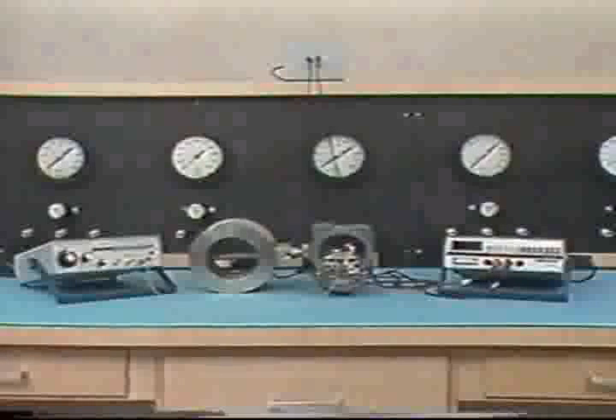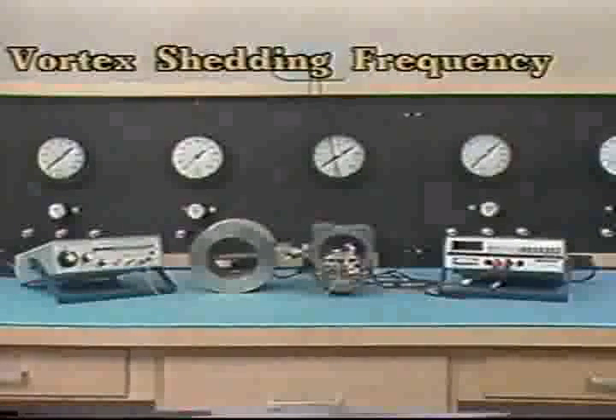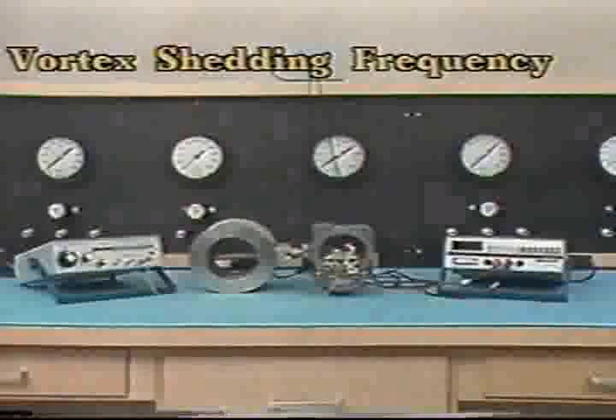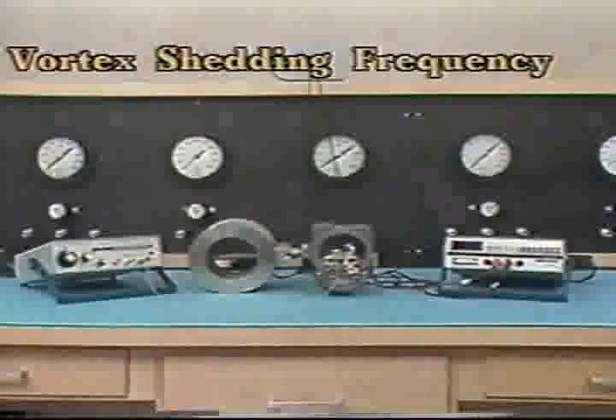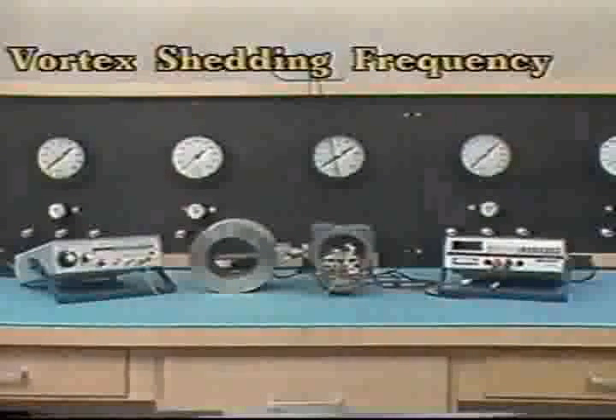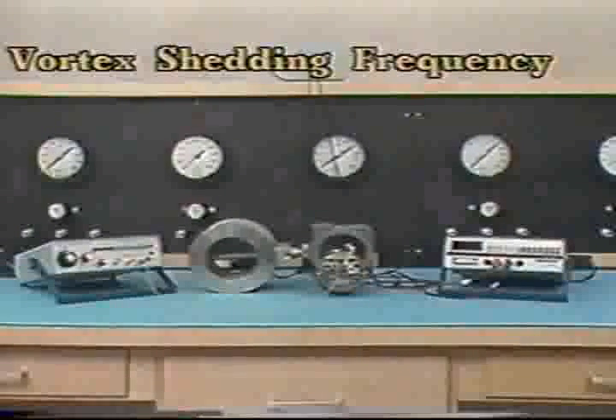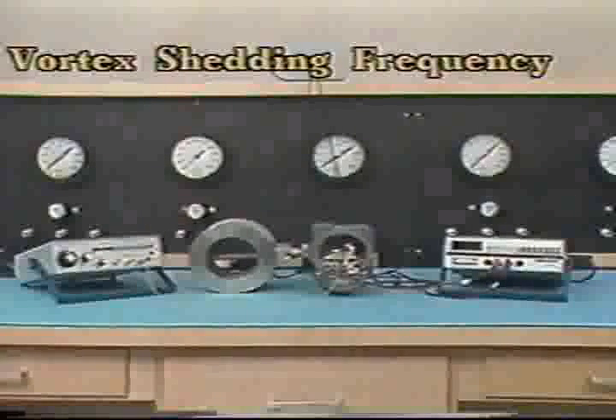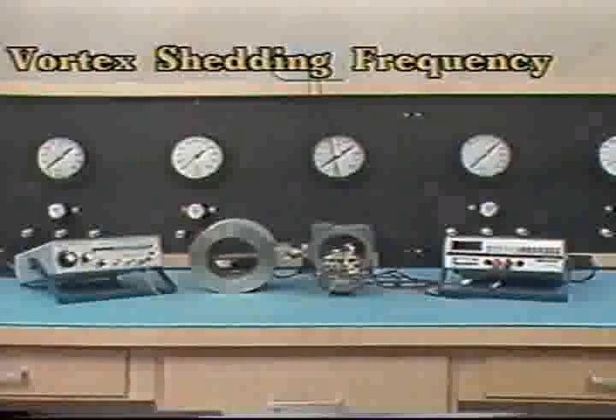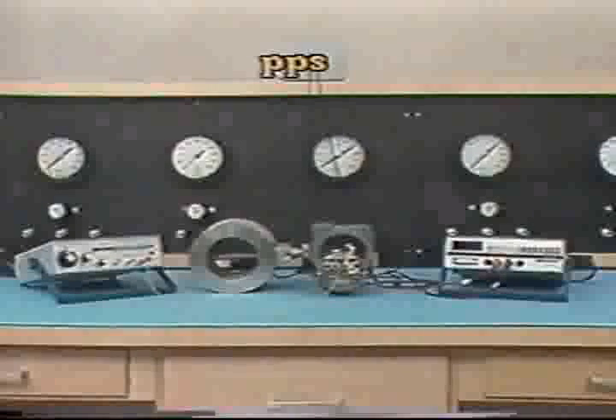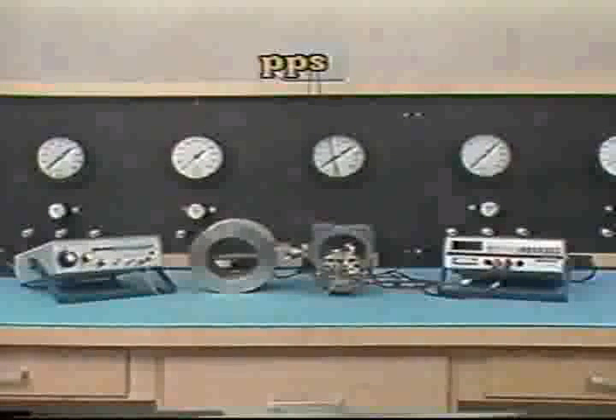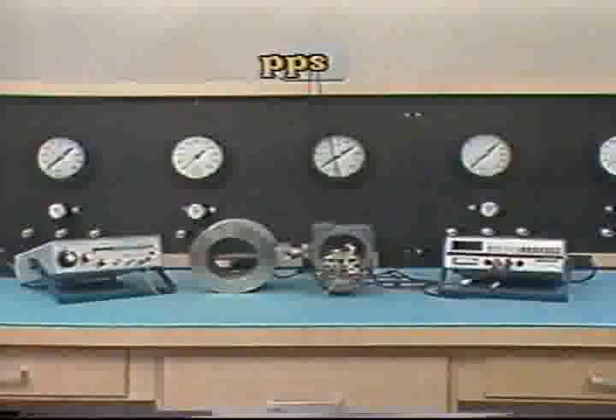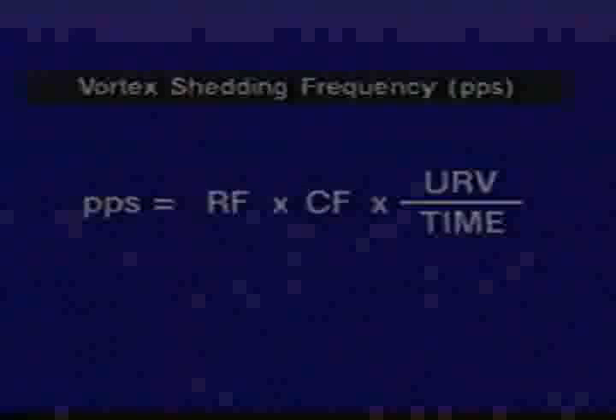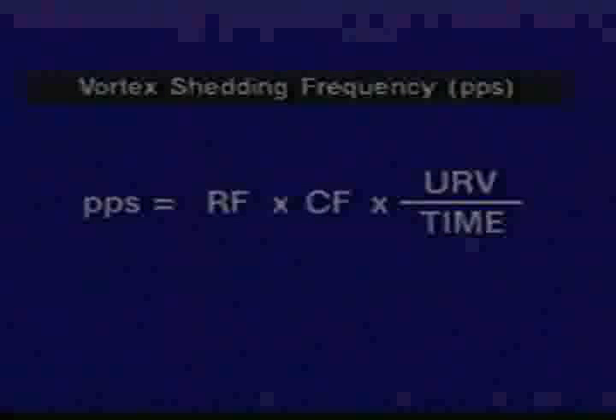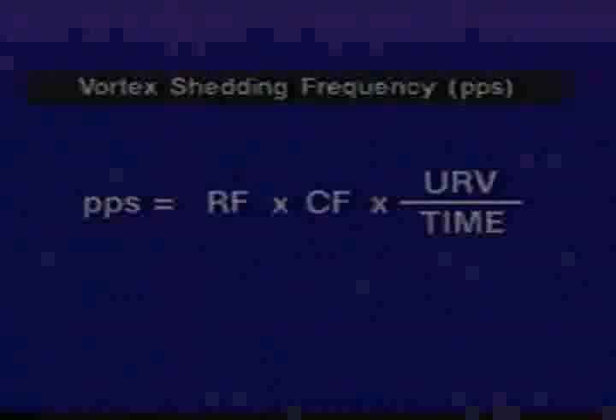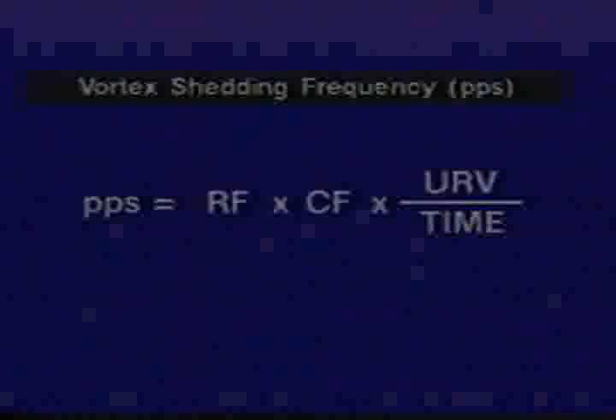Before the connections can be made, the vortex shedding frequency must be determined. The vortex shedding frequency is usually provided by the manufacturer. However, you may have to calculate the frequencies yourself. The vortex shedding frequency is represented in pulses per second, or PPS. Pulse per second represents the alternate shedding of vortices on either side of the bluff body. This formula is used to determine the vortex shedding frequency. Now let's apply some values to it.